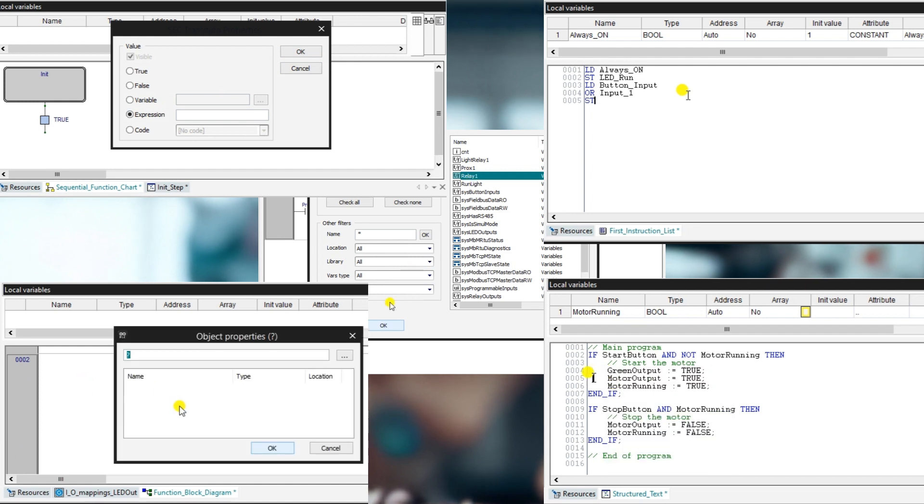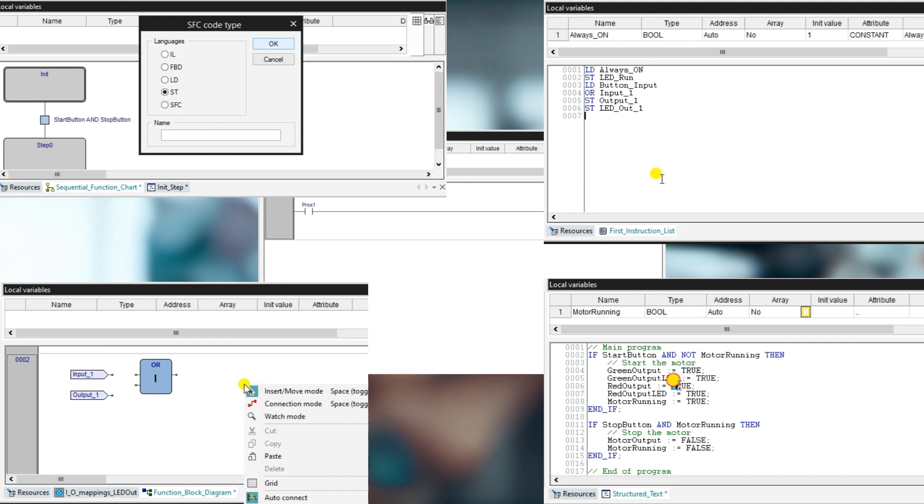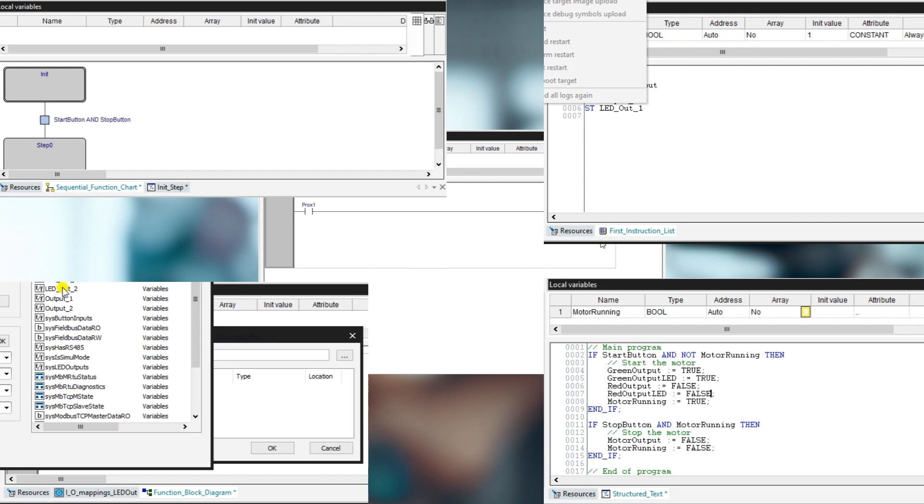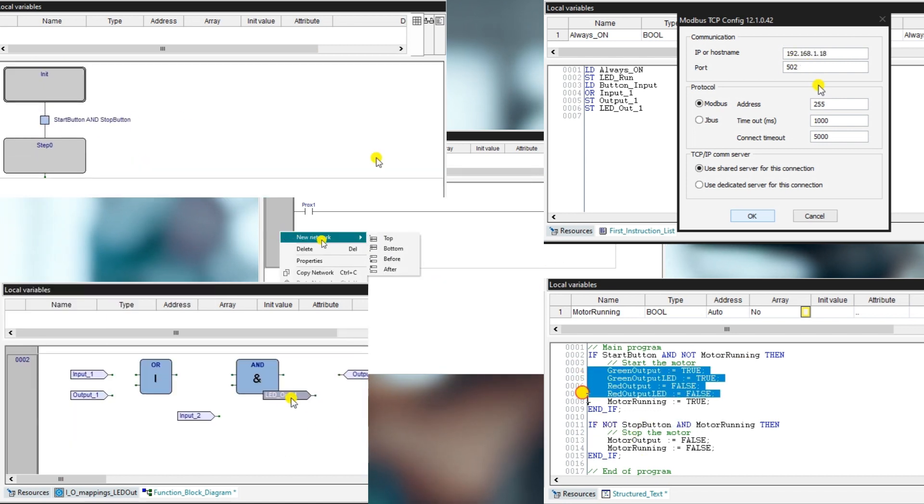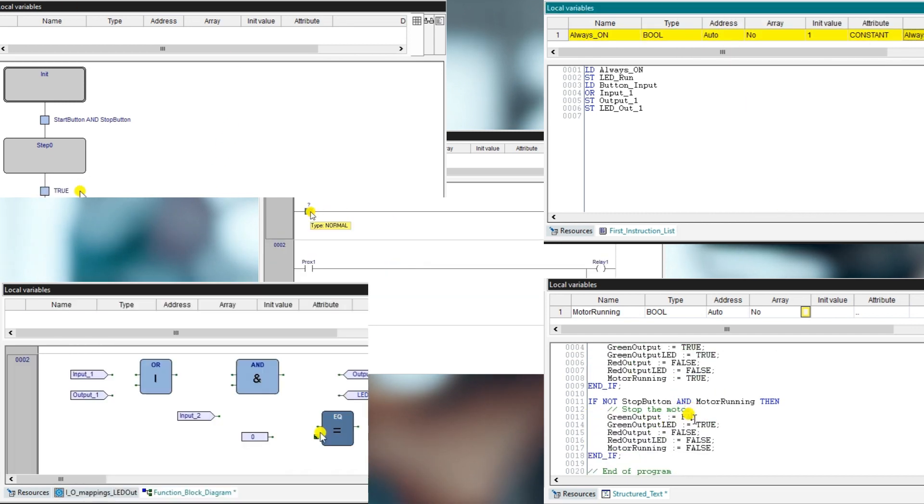This flexibility of the PLC programming environment allows you to adapt the PLC programming package to your specific application. However, it is essential to note that the PLC programming software is mostly manufacturer-dependent. This means that you need to purchase or download the programming software for the maker and model of your PLC, though Codesys is a software package that standardizes the PLC programming environment. Not all manufacturers agree with adopting this method. Apart from the actual programming of the controller, features of PLC programming usually include documentation stored on the PLC, online editing of the logic, and monitoring, display, and force variables in the PLC.